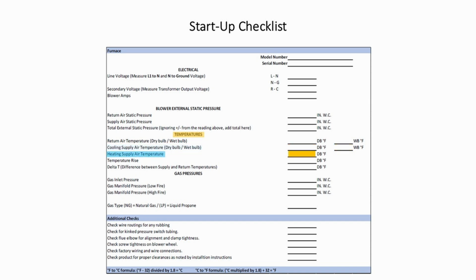Under heating supply air temperature, enter the dry bulb. Temperature rise: enter the dry bulb number. You can arrive at that number by subtracting the return air dry bulb temperature from the heating supply air temperature. And delta T, or the difference between the supply and the return air temperatures, goes here.